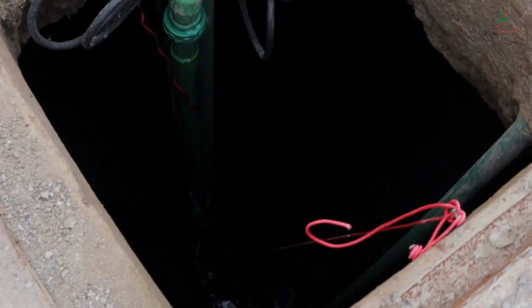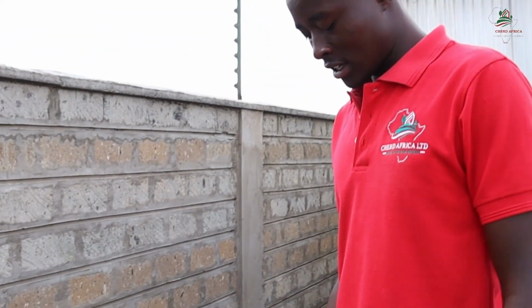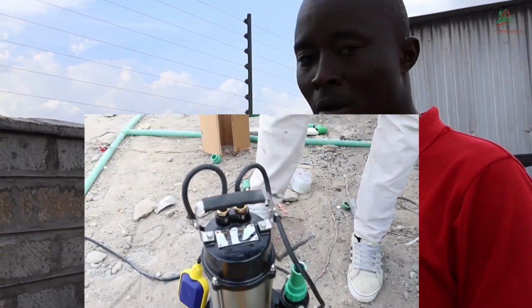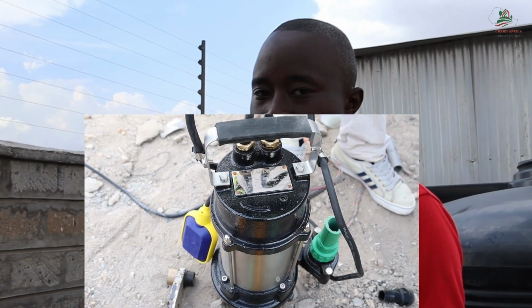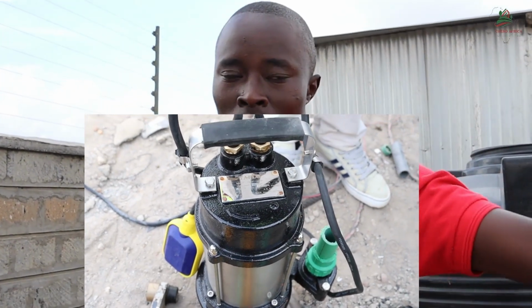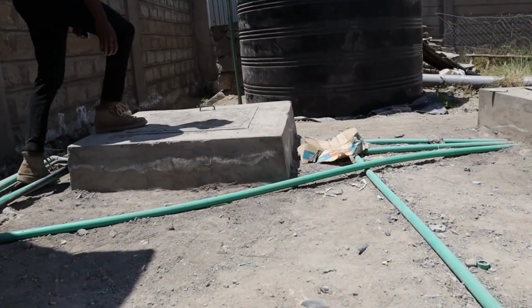The purpose of this collection manhole is that we don't have any disturbance in this chamber. So water settles here, and then we have introduced a submersible pump inside here. Any water you flush from the estate channels through those manholes up to this last manhole here, and it is pumped by this submersible pump to the filter.